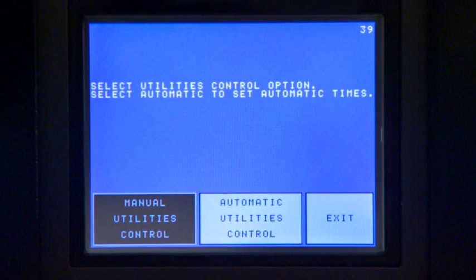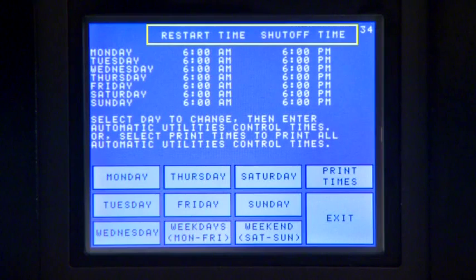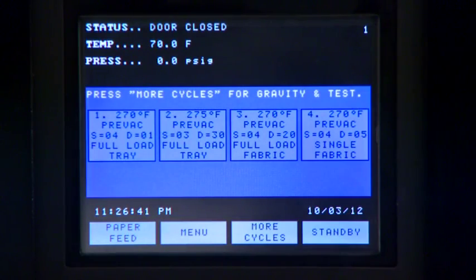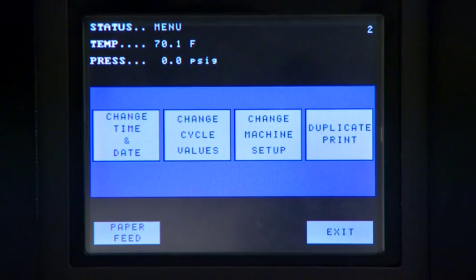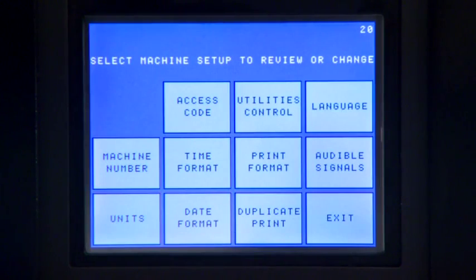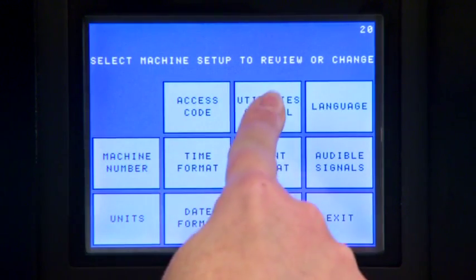You can also use the Auto Utility controls to program the sterilizer to automatically shut off its steam and water at the end of the day to conserve utilities. Shutdown and power-up times can be programmed for any time of the day on weekdays or the weekend. To set up this function, press the Menu button from the main status screen. Press the Change Machine Setup button. Then the Utility Control button.